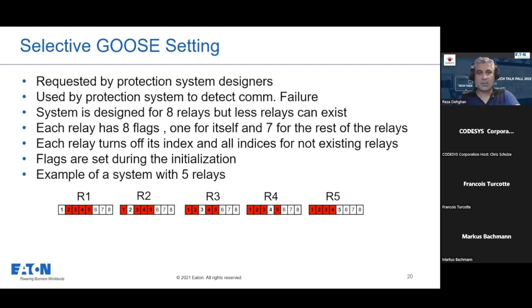Each relay has 8 flags. This is the way the SMP gateway logic will program the protection relay. For each relay, we have 8 flags, 1 for itself and 7 for the rest of the relays. Each relay turns off its own index and all the indices for non-existing relays. Flags are set during initialization. As an example, we have 5 relays instead of 8, so relays 6, 7, and 8 are missing. On R1, the first relay, we set 1 for that relay, and we also set 6, 7, and 8. So on all the relays, we set 6, 7, and 8, and we also set the index for that specific relay. Next page.